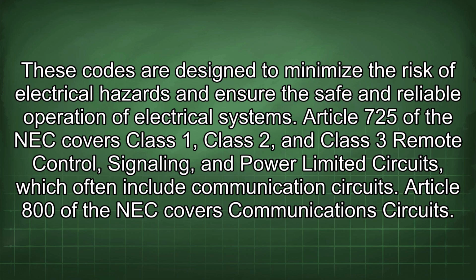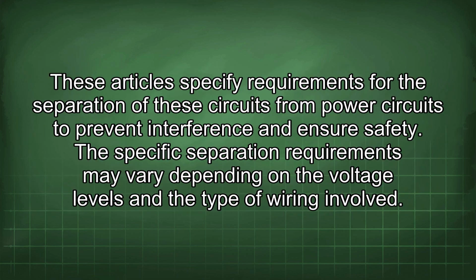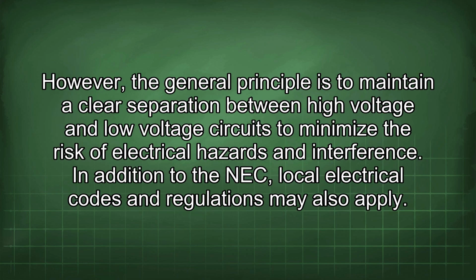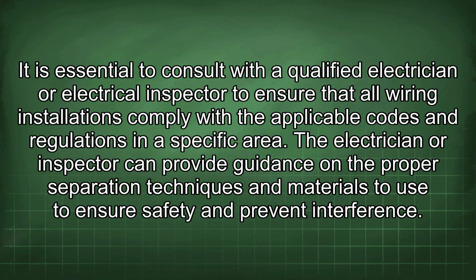Article 800 of the NEC covers communications circuits. These articles specify requirements for the separation of these circuits from power circuits to prevent interference and ensure safety. The specific separation requirements may vary depending on the voltage levels and the type of wiring involved. However, the general principle is to maintain a clear separation between high voltage and low voltage circuits to minimize the risk of electrical hazards and interference. In addition to the NEC, local electrical codes and regulations may also apply. It is essential to consult with a qualified electrician or electrical inspector to ensure that all wiring installations comply with the applicable codes and regulations in a specific area.